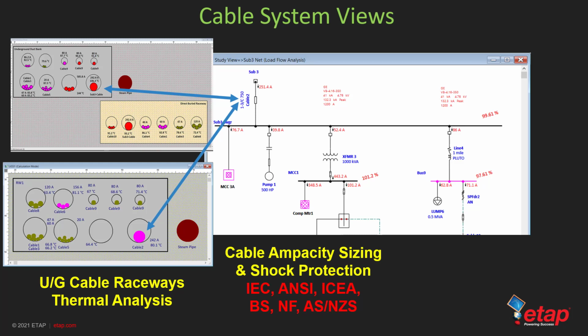And I'm going to show you here that the same cable from one line diagram can be placed in an underground duct bank or an underground raceway, the direct burial system. And you can run the thermal analysis on those, and it would be telling you exactly what the temperature is going to be and the effect on the adjacent cables and the different conduits or locations.